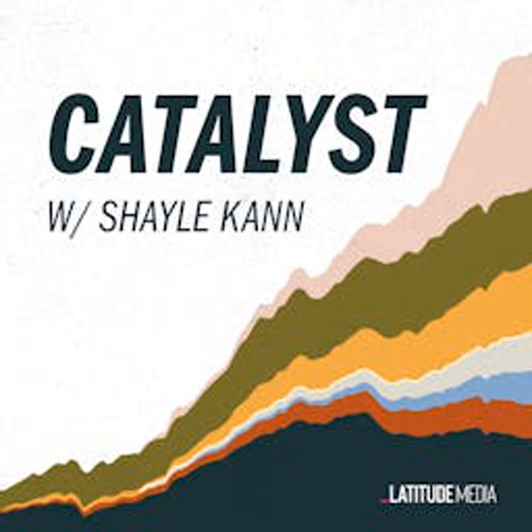The other thing, and it's not just the inverters, it's actually the transformers. From some statistics we've learned, transformers are not really designed to run at their rated power as long as they do in these desert power plants, where they're very hot because they're sitting in the sun, and they're running at nameplate rated power for 8 or 9 hours a day. So they are failing about 1%, 1.4% per year on average. And that transformer that's pretty hard to replace needs to be replaced. If you have 100 transformers on your utility solar facility, you're replacing a transformer or more a year. And that's not fun. And the last thing is they have no monitoring. There's no real intelligence built into these transformers.